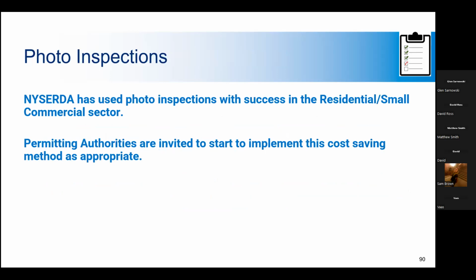So NYSERDA has implemented photo-only inspections with a lot of success. They can be a great cost-saving supplement to a process that's already underway. If an inspector can review photos that tell the story of an installation, this can save the inspector time by not having to climb on the roof or open every single enclosure. Like I said, inspectors can complete the inspection in less time and spend more time in areas they've identified as potentially problematic. If there are trenches or walls that will be closed up by the end of the installation, the inspector can look at the pictures and not have to go multiple times to a site.